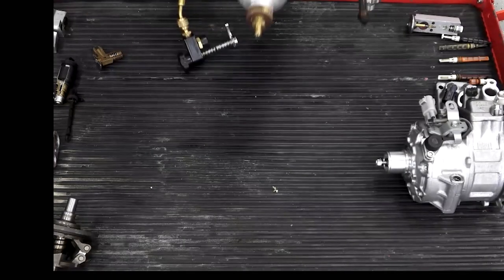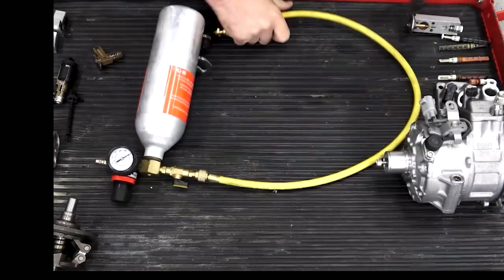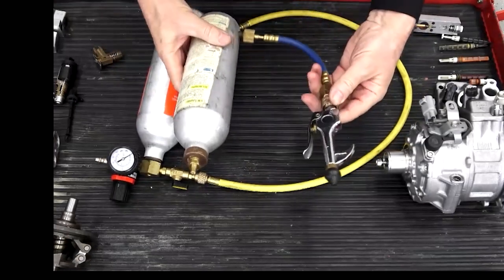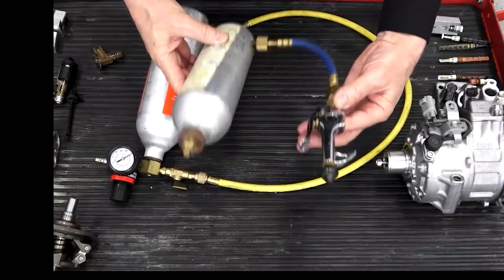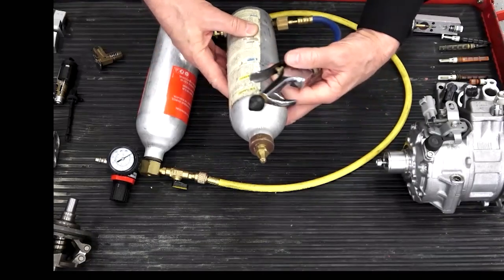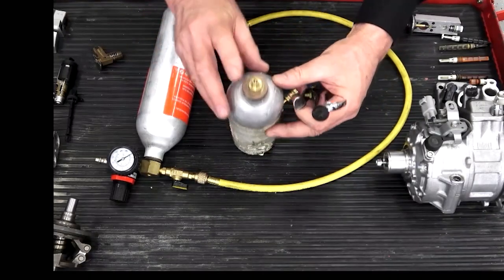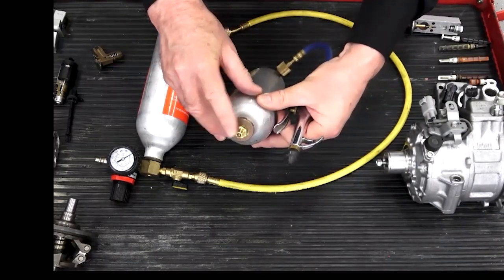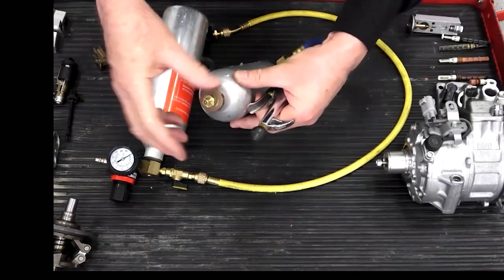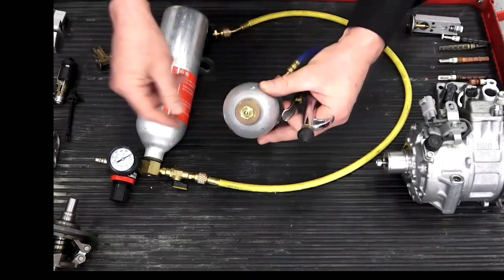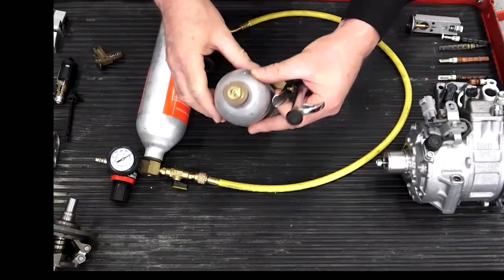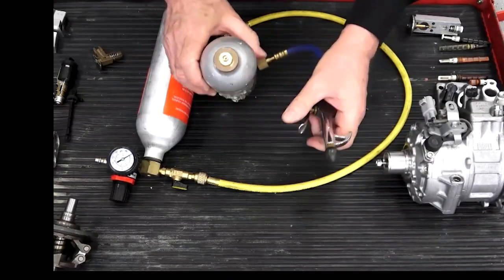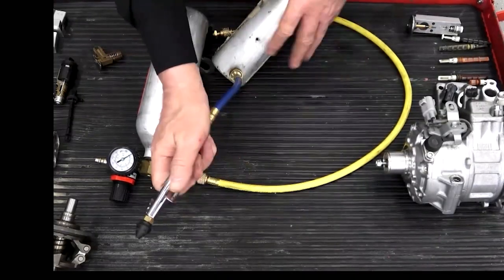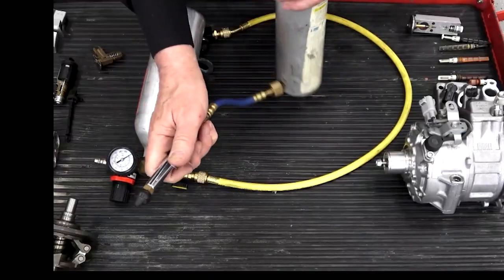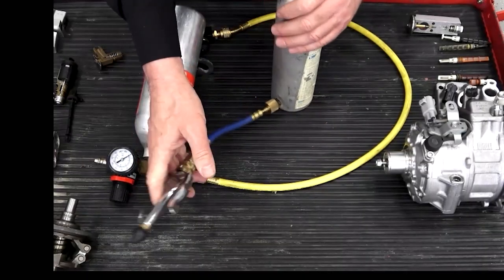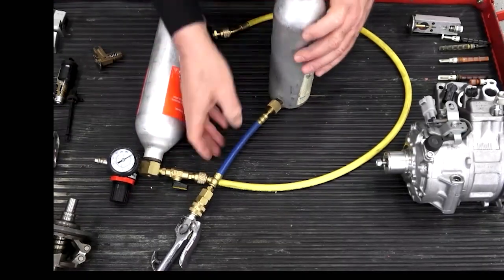About flushing tools. I try to get out in the field as often as I can. I walk into a lot of shops, and this is the flush tool that they're using. It has a port on here where I can use an air chuck. So I put a quart of solvent in here, charge it with maybe 50, 60 pounds of static air pressure, and then I hold this rubber blower tip up to the evaporator outlet, hit the button, and try to flush the evaporator.